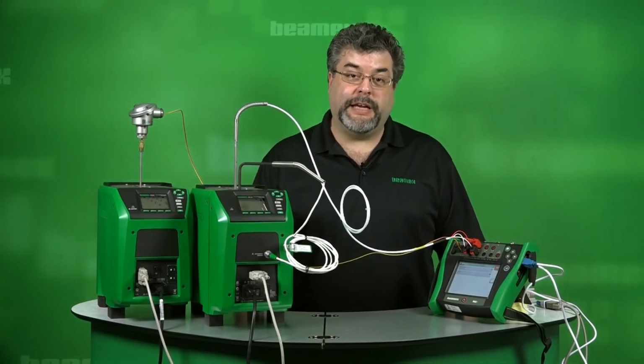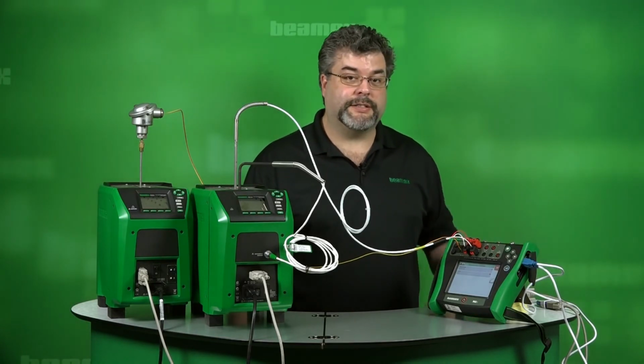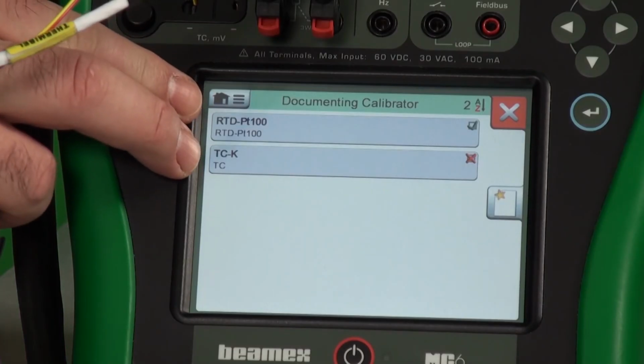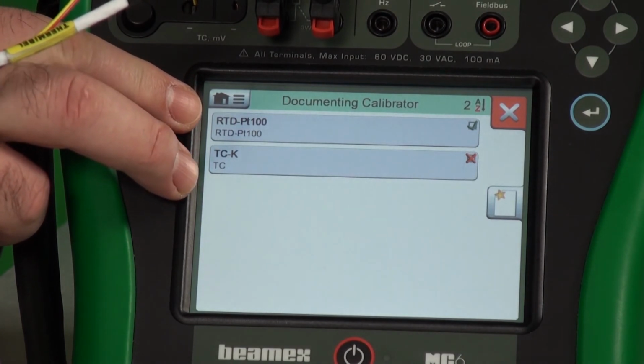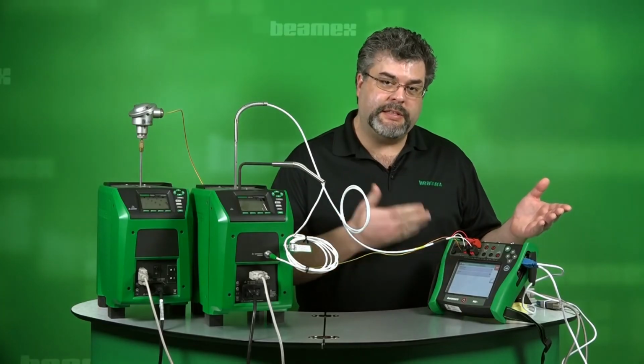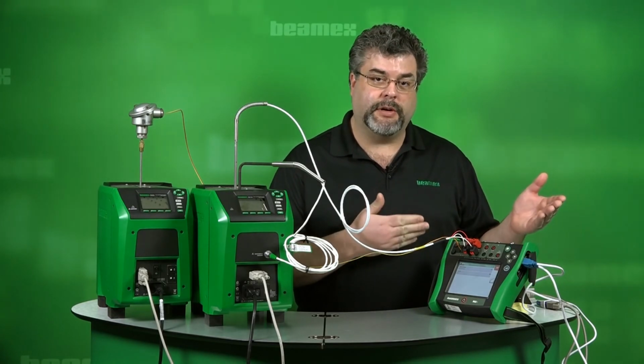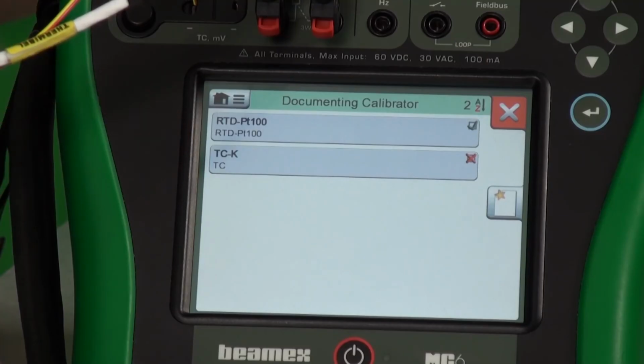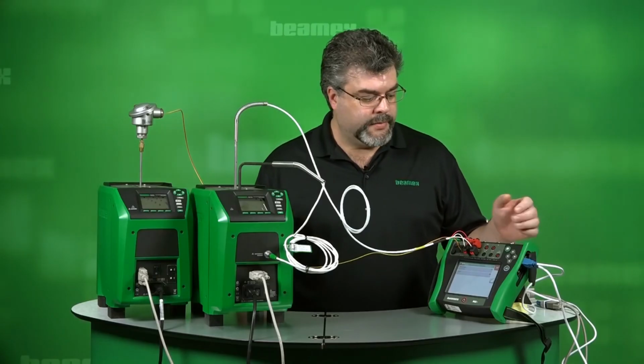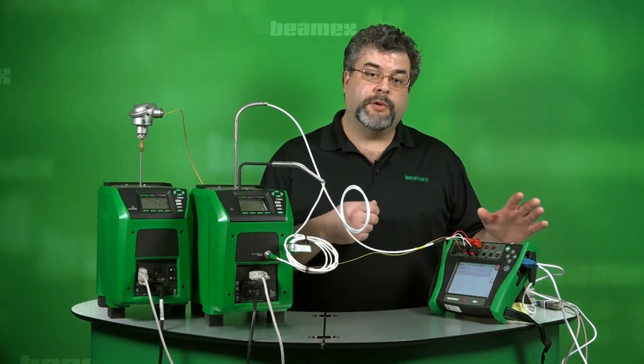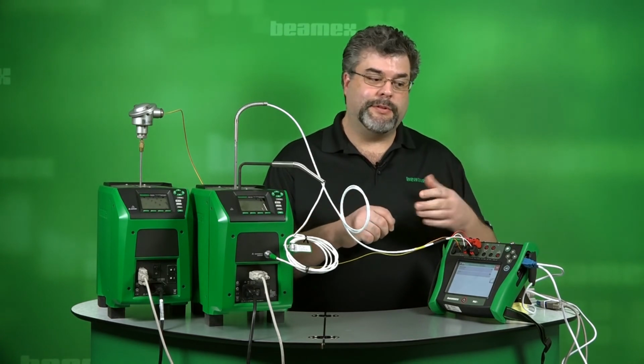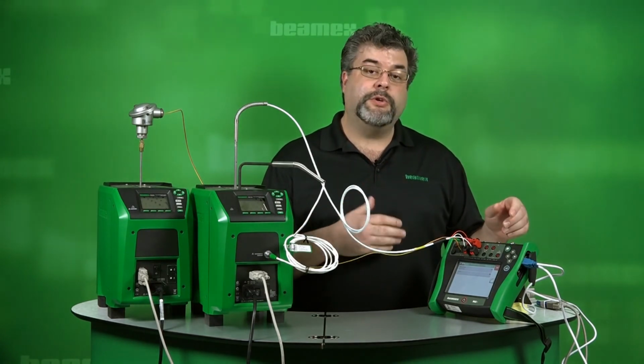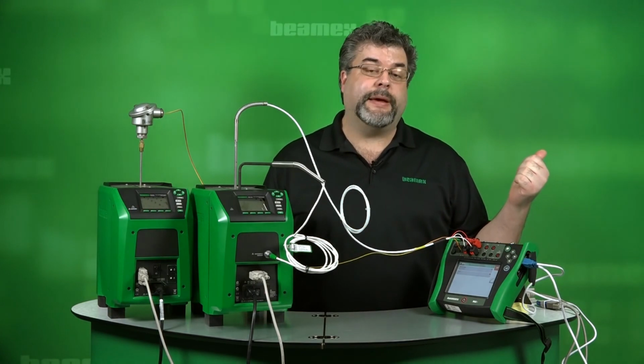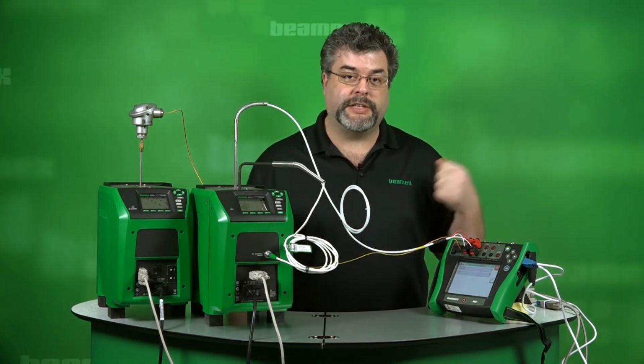We have our calibration data now. It's stored right in the MC6. We have our 2 tests, the RTD, passed. We have a green check mark next to that. That means that it's been tested and it passed based on our error allowed. The thermocouple has a red X next to it. That means that it was tested as well, but it failed based on our error allowed. The data can be transferred over to another system. You can write it down on a piece of paper, you could type it into another system, or you can automatically upload it into our CMX calibration software for a paperless setup.